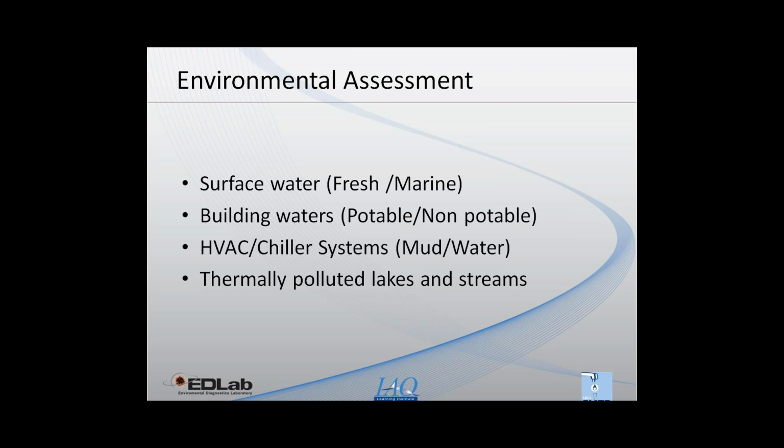The indoor versus outdoor mechanism is another important factor. If you are evaluating Legionella growth inside the environment, then you should be paying attention to the tap, shower head, valve, eye wash, safety shower, pipe work material, etc., and HVAC, evaporating coil, humidifier. These are some main sources where this bacteria can grow. While outside, this bacteria can flourish in ornamental fountains, especially when the temperature is a little bit higher.